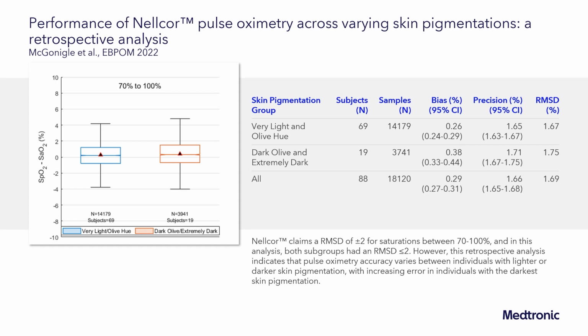we, specifically within Nellcor, looked at validation data over different pigmentation subgroups. When we broke out all of our validation data into light pigmentation and dark pigmentation, and then analyzed that performance, that error, so the SpO2 minus the SaO2, the arterial oxygenation reference, what we found is that for light and dark, they both met our accuracy specifications of less than 2 RMSD, and that's between 70 and 100% saturation.